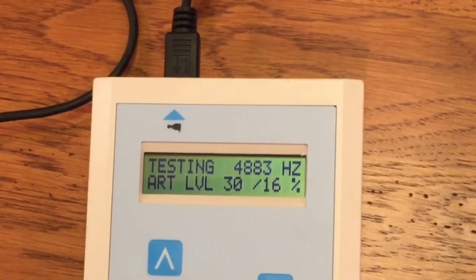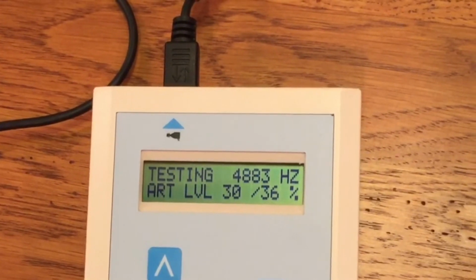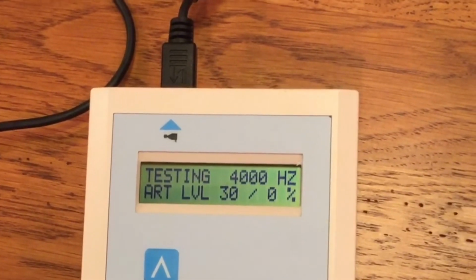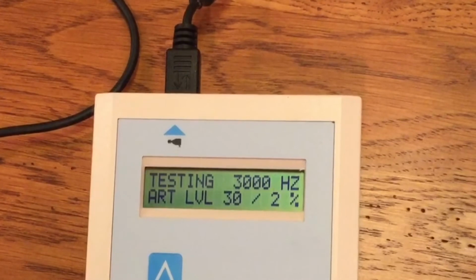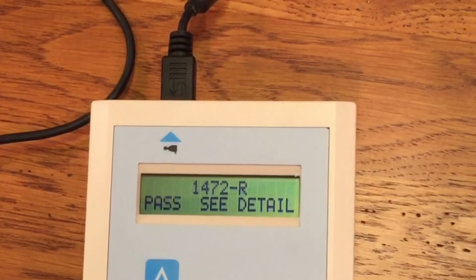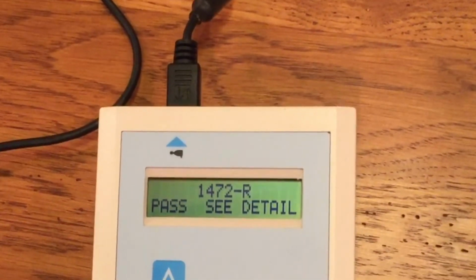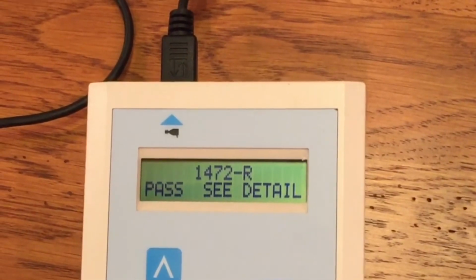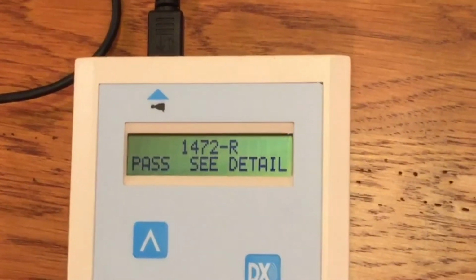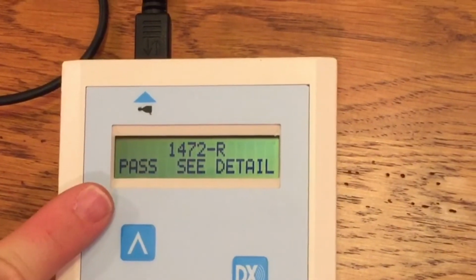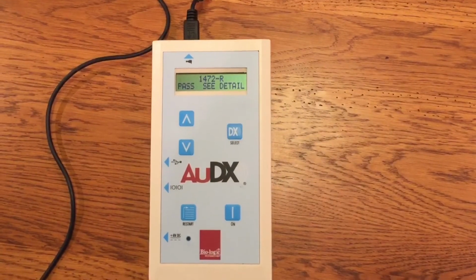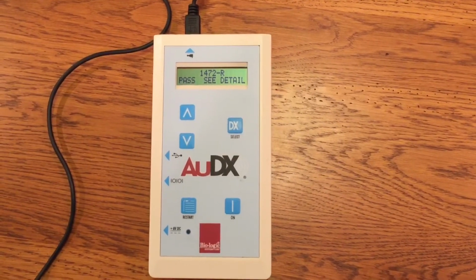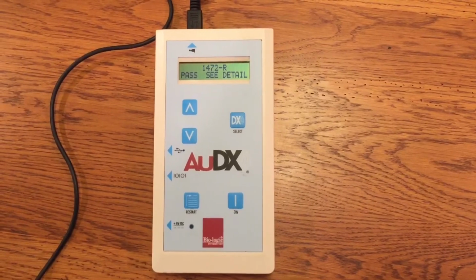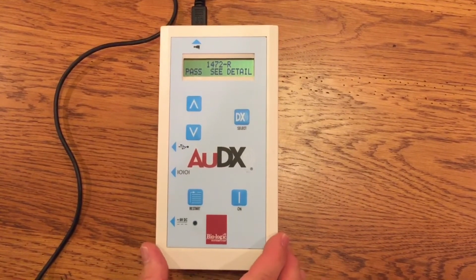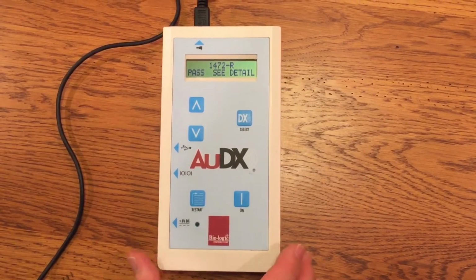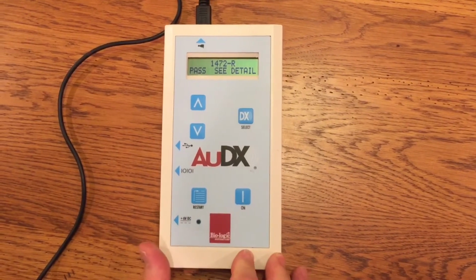Now let's stop the noise. Okay, so the test didn't progress as long as the noise was going, but as soon as we stopped, it went ahead and tested, and we have a pass. If we would have kept the noise going, the machine would have eventually stopped and given us an error message of high artifacts or too much noise. We would have needed to have made adjustments in the environment and then retested.